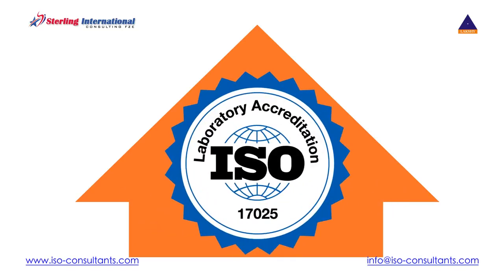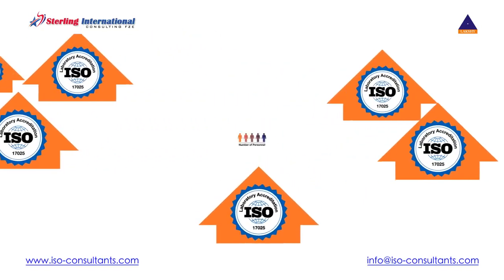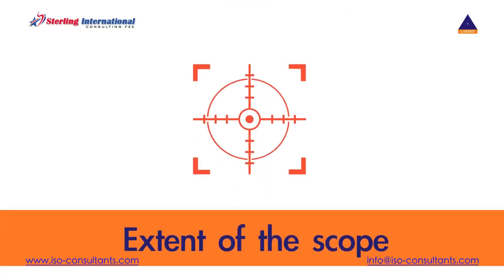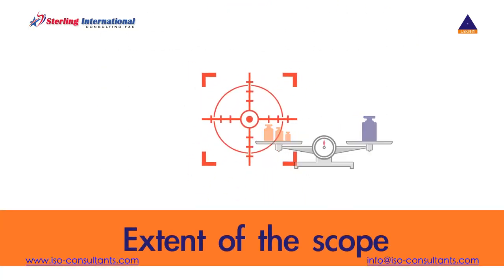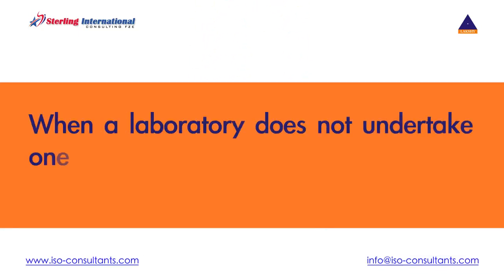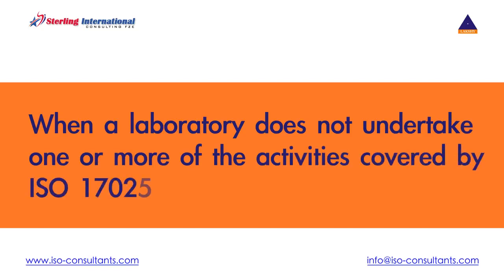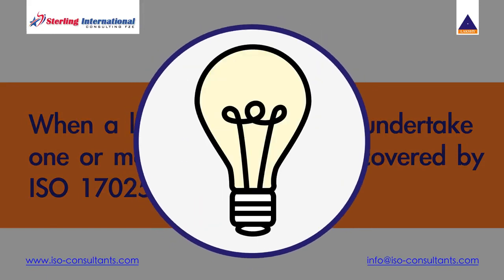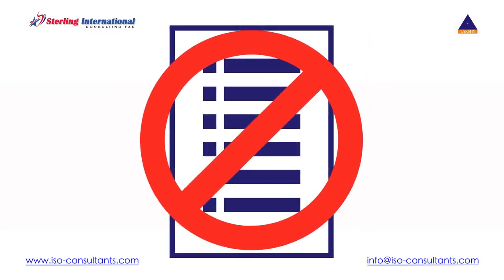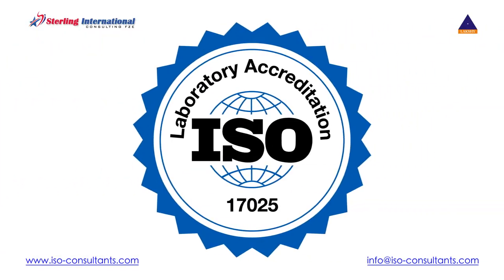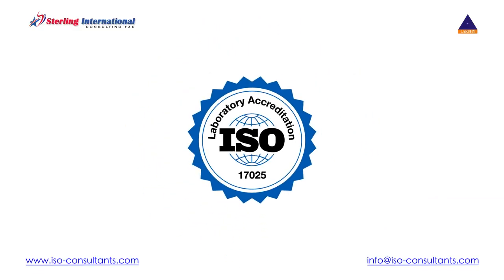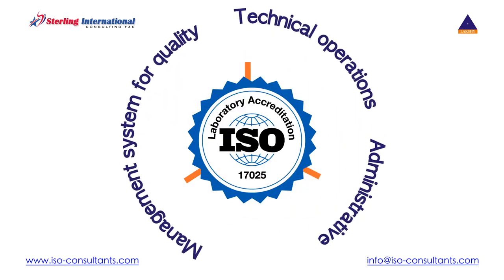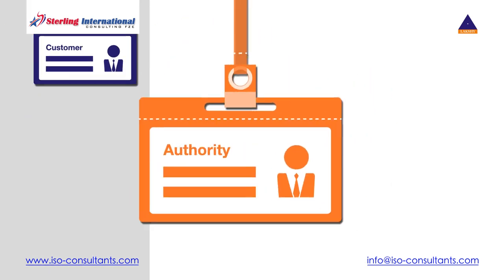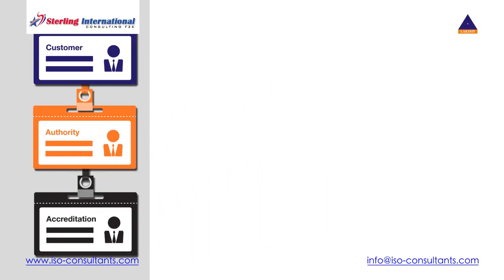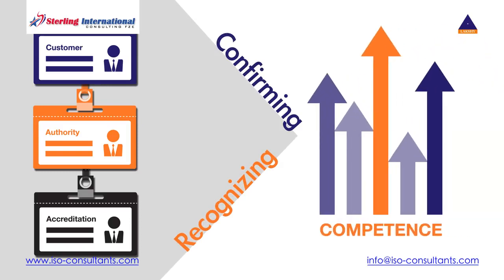ISO 17025 is applicable to all laboratories, regardless of the number of personnel or the extent of the scope of testing and/or calibration activities. When a laboratory does not undertake one or more of the activities covered by ISO 17025, such as sampling and the design development of new methods, the requirements of those clauses do not apply. ISO 17025 is for use by laboratories in developing their management system for quality, administrative, and technical operations. Laboratory customers, regulatory authorities, and accreditation bodies may also use it in confirming or recognizing the competence of laboratories.